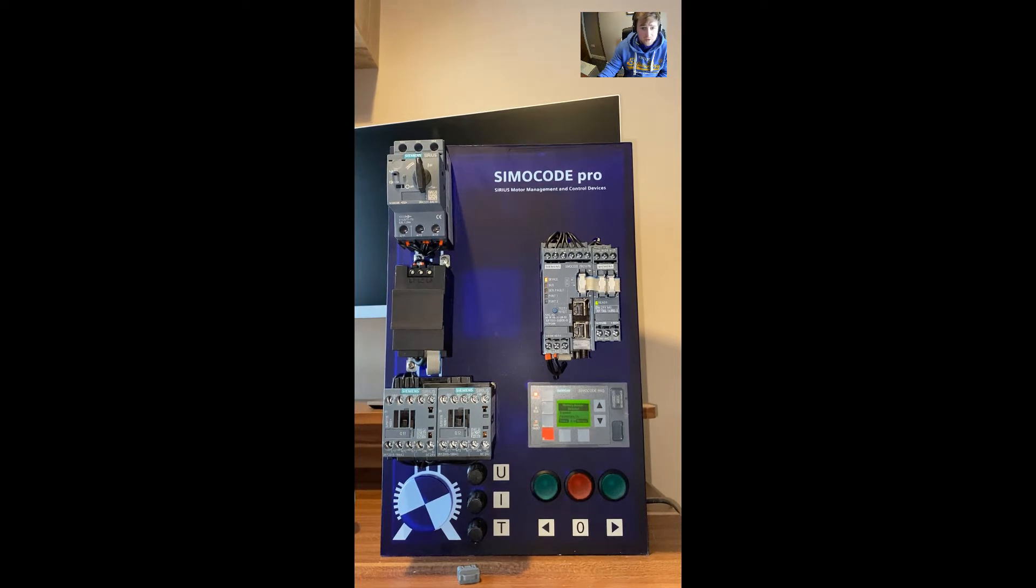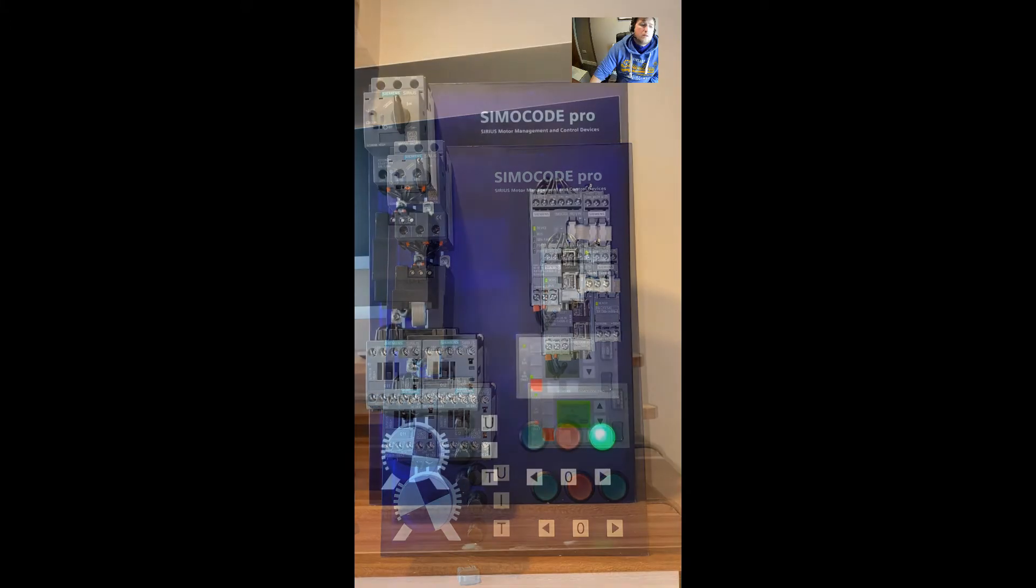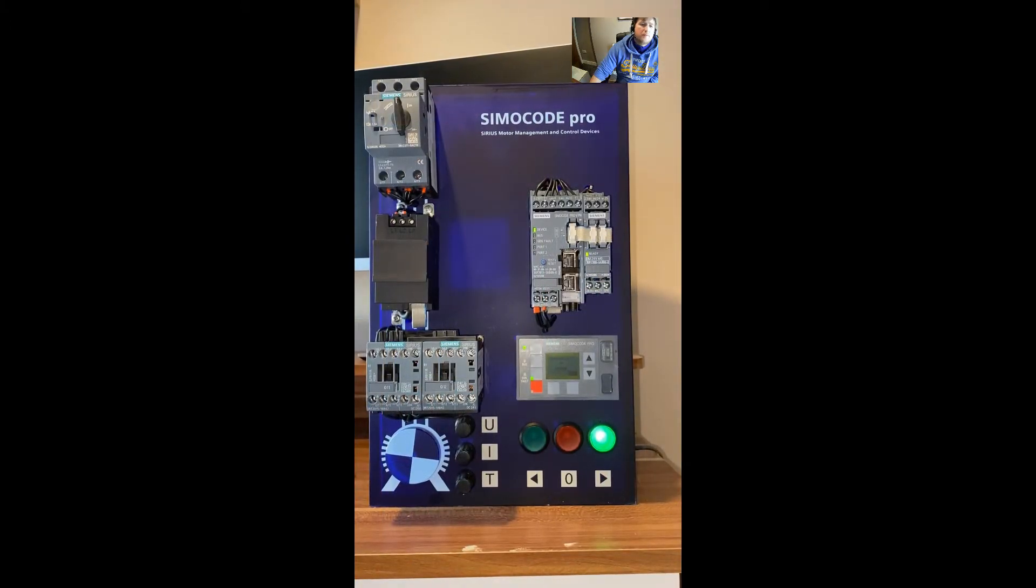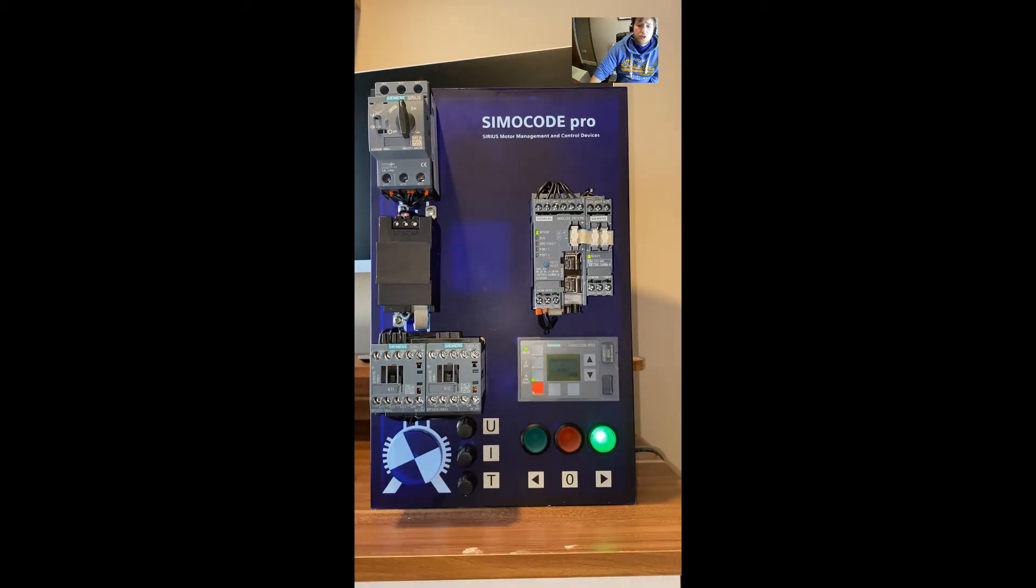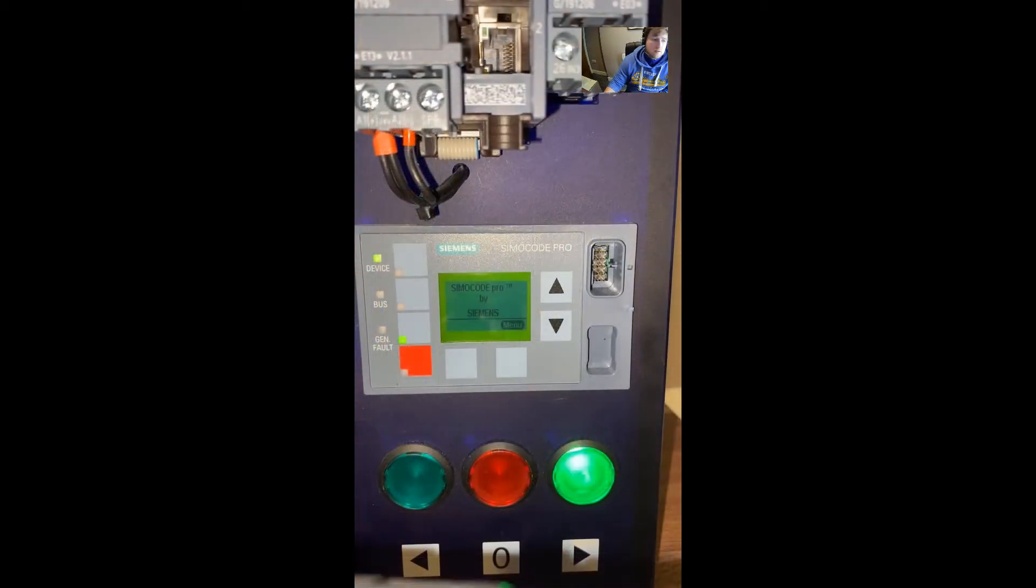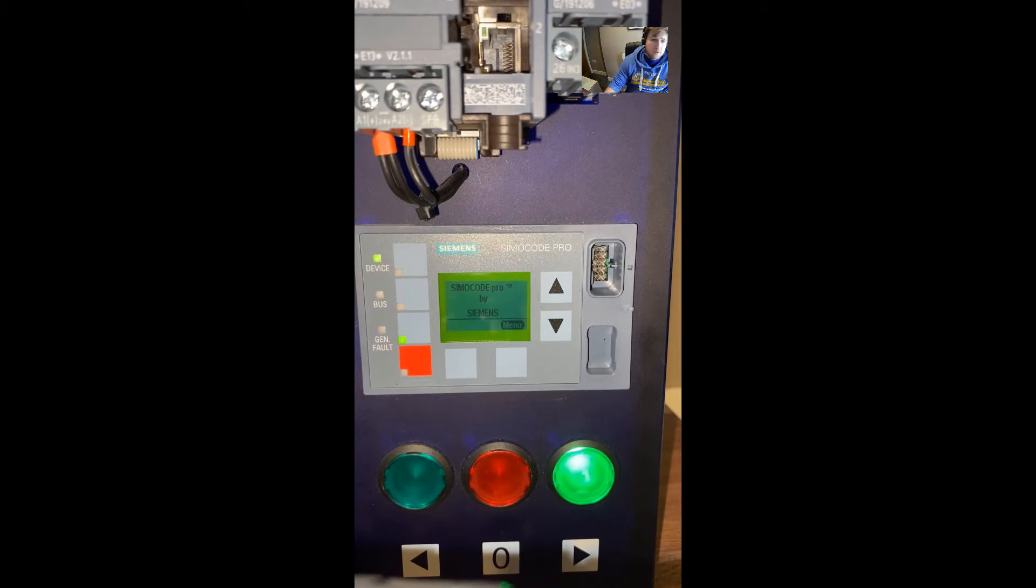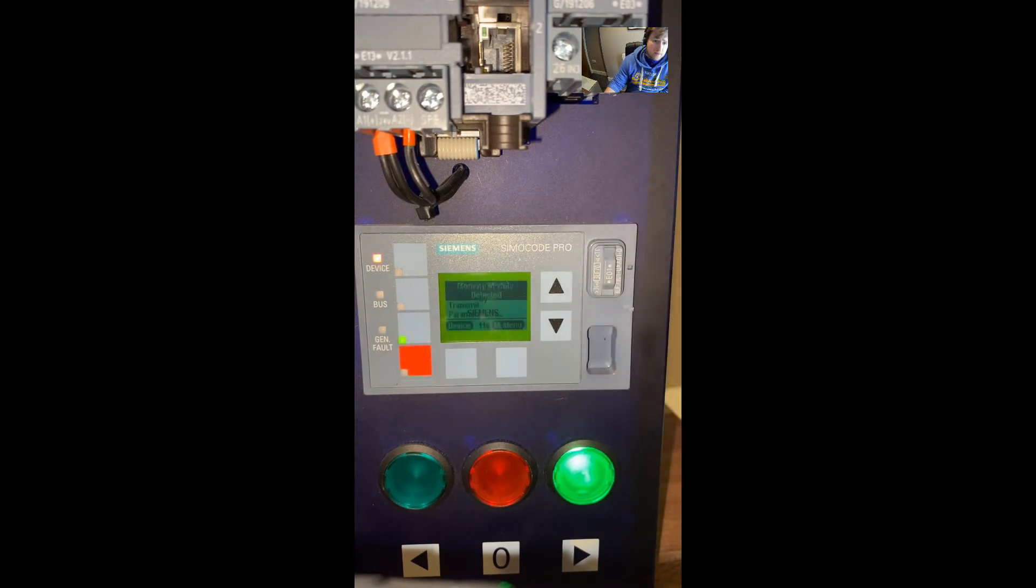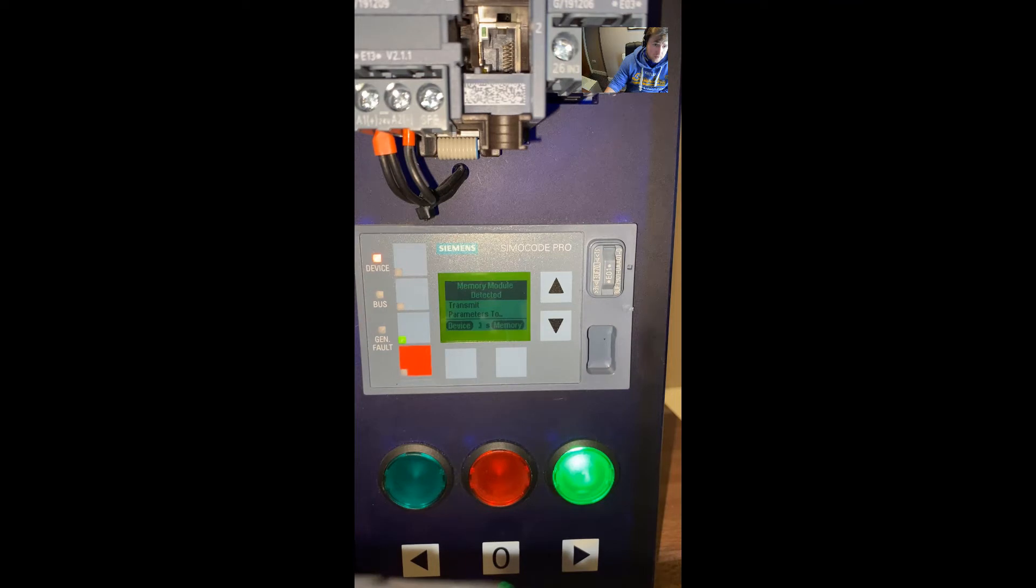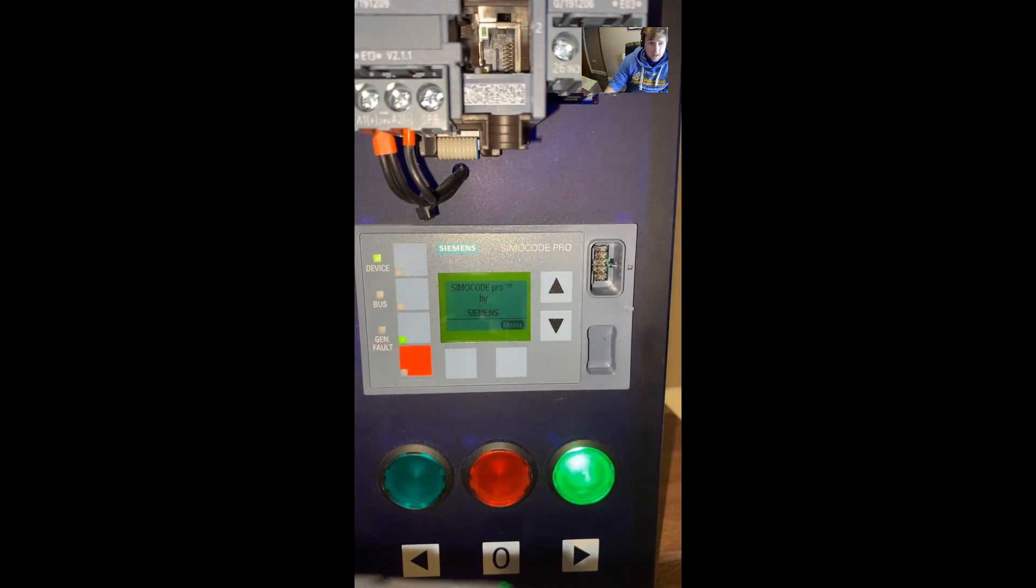We now have a fully operational SIMOCODE system and we're good to go. The HMI is now visible and the blanking plate has been removed. We're adding in the memory card and straight away you get this countdown clock which signifies how long you've got to select one of these two options: device or memory. Memory takes the program to the memory card, or device takes the program from the memory card to the actual device.